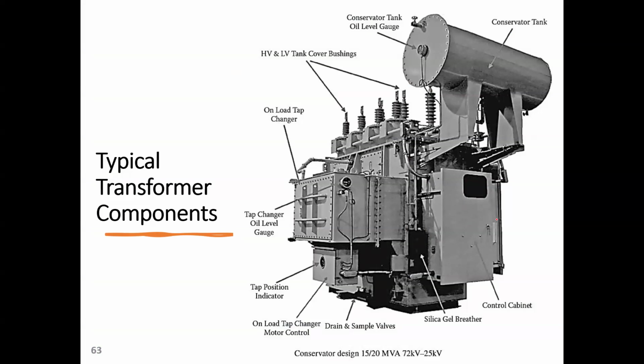Here, guys, in this shape, we can see a complete transformer. This is a high voltage transformer. The transformer you can see here is 15 to 20 megavolt ampere. So this type of transformer is designed for these power levels, 15 to 20 MVA. And the voltage level of the primary side is 72 kV. Or sorry, guys, this is maybe a step down transformer. Yeah, so 72 to 25. This can be in some step down transformers in substations. So this is 72 to 25.